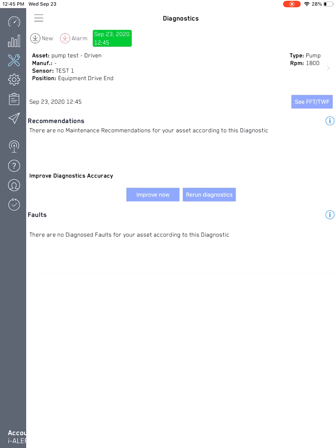Once you download the new FFT, the diagnostics will be done automatically, and then you can see this one has no maintenance recommendations for your asset according to the diagnostics. You can then pretty much know that this one has no real faults associated to the spectrum. If you do have any issues with faults, it will show all the information right on this page under the diagnostics option in the menu bar.